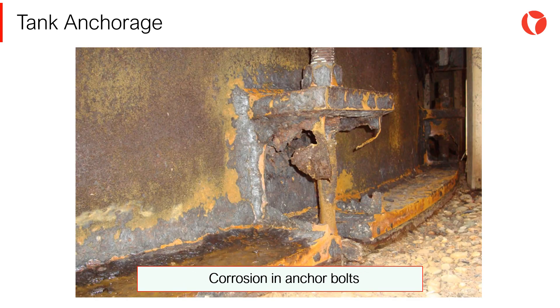It is worth mentioning that corrosion does not occur exclusively inside the tank. The material of the anchor bolts should be selected according to the corrosiveness of the environment. The figure shows a totally corroded bolt due to poor material selection.